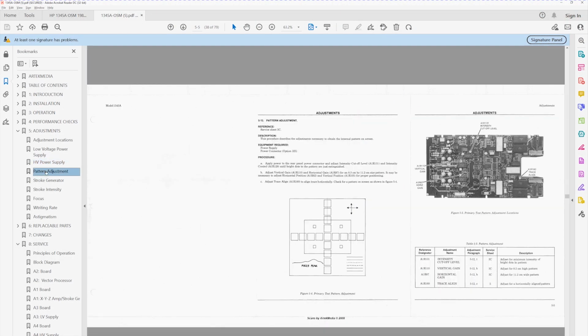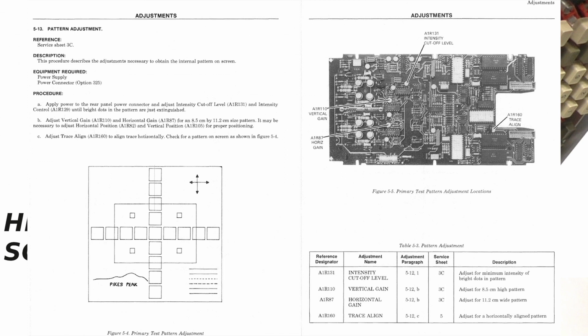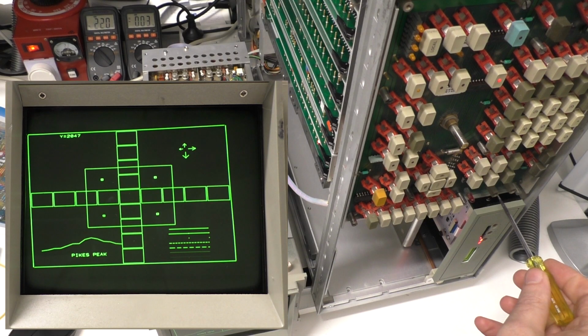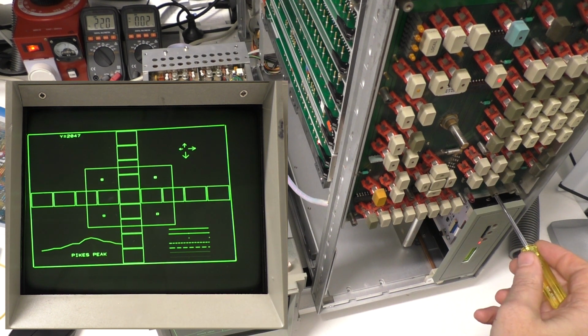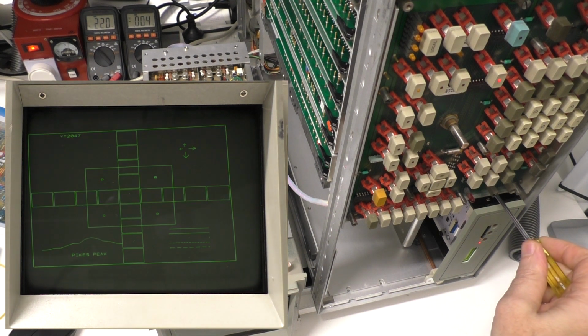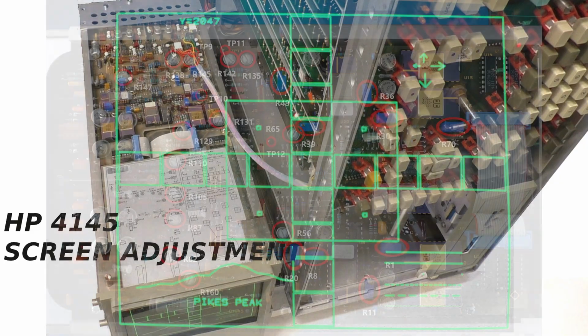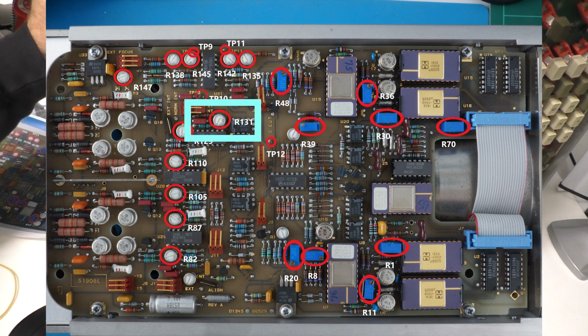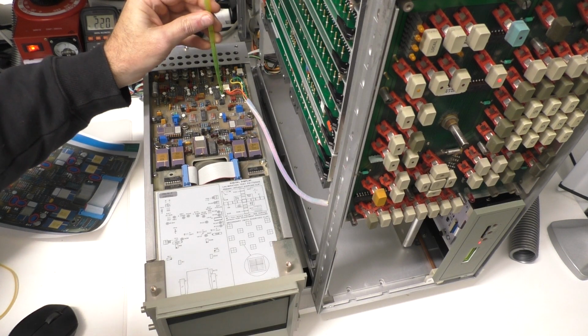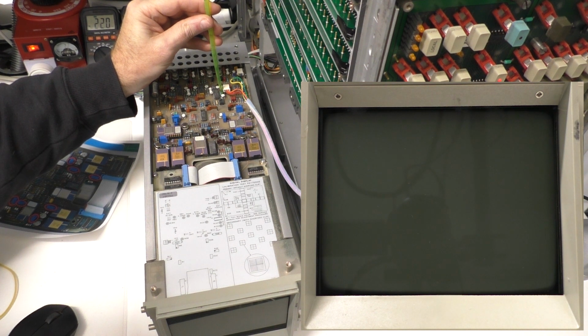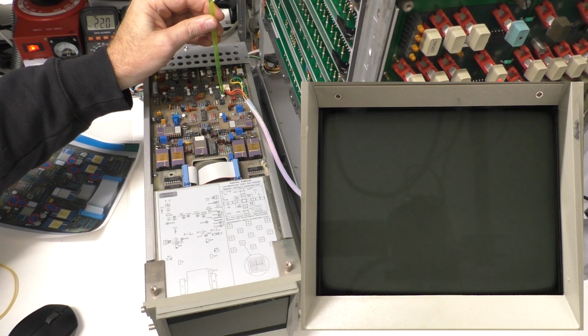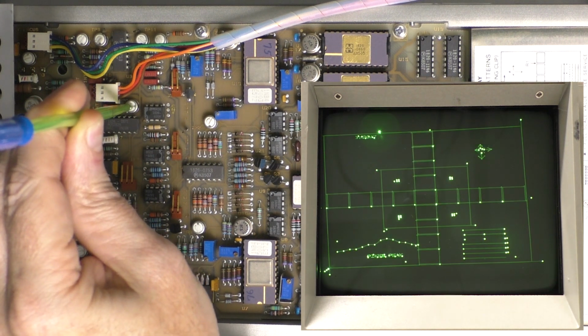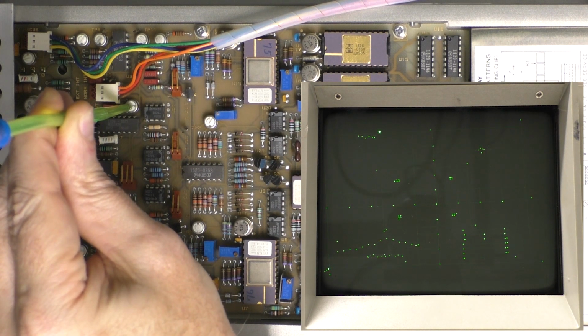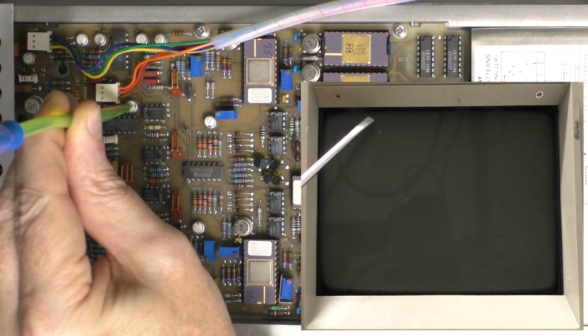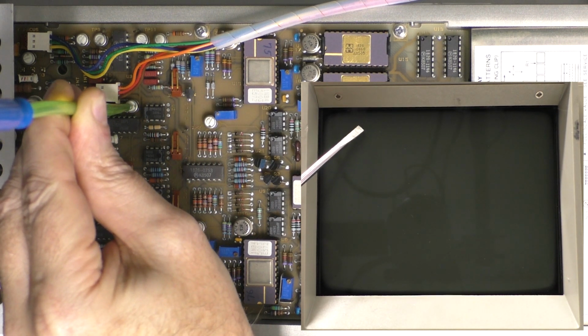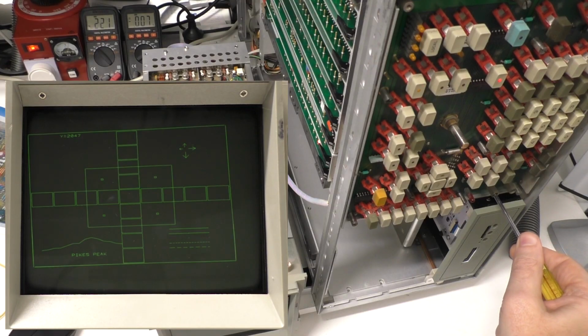We will follow section 5-13, pattern adjustment. 5-13-A, intensity cutoff. Turn the intensity control on the front of the unit all the way down. This is the trimmer underneath the measuring lead. Locate R131 on the A1 board. This is the intensity cutoff. Adjust this trimmer until the brightest dot is just extinguished. You can now readjust the intensity trimmer to see the image.